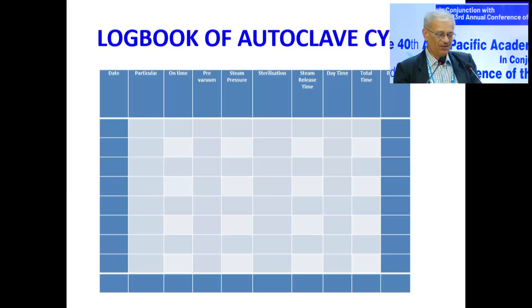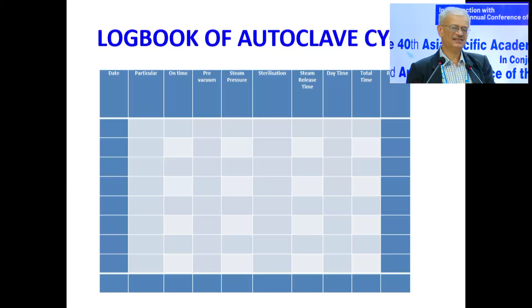There's a logbook of autoclave cycles that need to be maintained. It's called mechanical monitoring of autoclaving, and what time the heater was turned on, what time we reached the required temperature and pressure, and what was the holding time. All that needs to be recorded, because as Dr. Chandrasekhar said, class 1 indicator only indicates that the temperature was achieved. So here at least the logbook will tell us that the cycle was run properly.